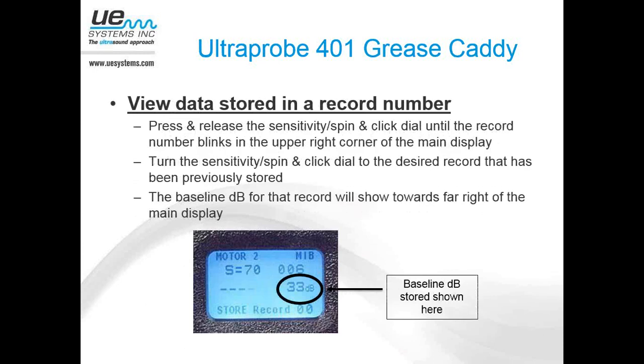Now, if we need to view data stored in a record number, what we're going to do is press and release the sensitivity spin and click dial until that record number blinks, like we did if we were advancing forward or scrolling back to correct ourselves. And then we turn the sensitivity spin and click dial back to the desired location. What's going to show here, you can see we've got a decibel level reading. This is the baseline dB that has been stored for that reading. That information comes over from UltraTrend DMS when we load a route into it. So we can see the baseline dB for, in this example, the motor 2 motor inboard point, and in this case it was 33 dB. So whatever the baseline is for those points, that's what's going to come over from DMS.